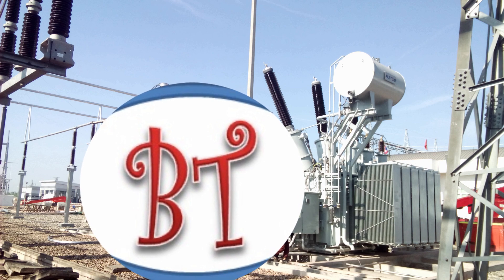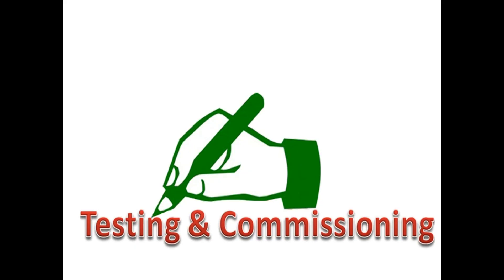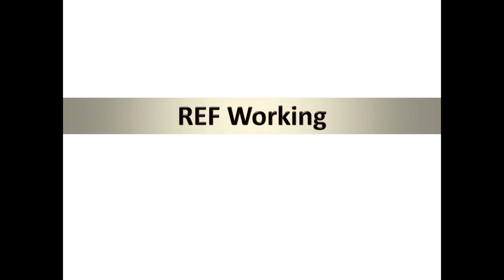Hi, welcome to Barney Tech channel. Here we are going to see the working of REF high impedance protection. First we will see the definition of REF. The REF is the restricted earth fault protection, a sensitive way to protect a zone between two measuring points against earth fault.